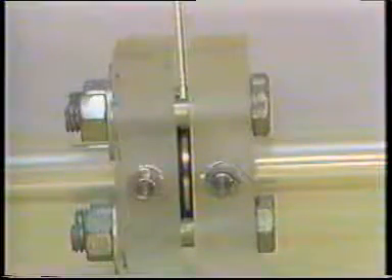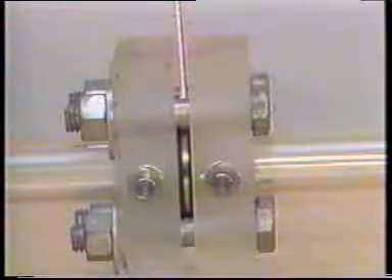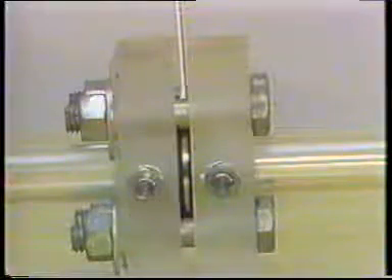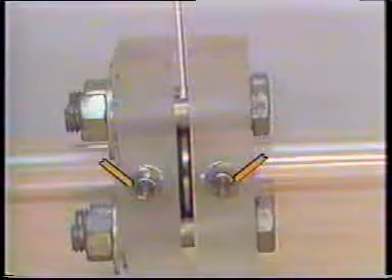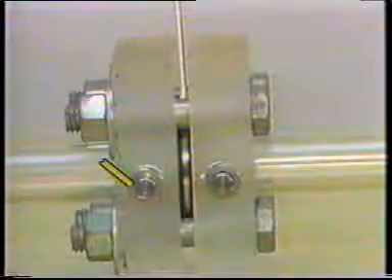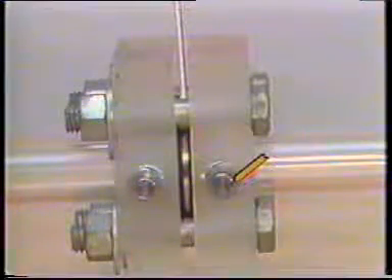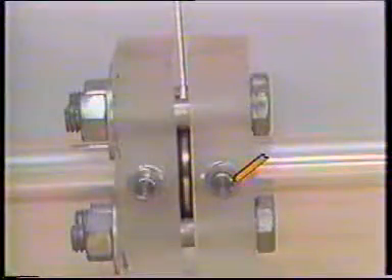In many applications, the pressure taps are installed in orifice flanges instead of being installed in the pipe. These flanges are specifically designed for flow measurement. The taps are located on each side of the orifice plate. The upstream or high side tap is located 1 inch from the orifice plate, and the downstream or low side tap is located 1 inch from the orifice plate.